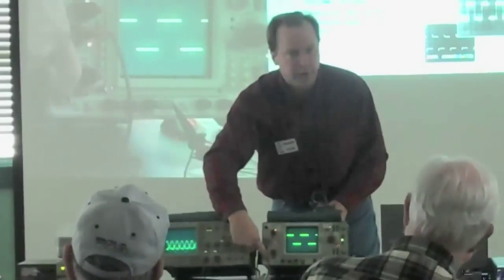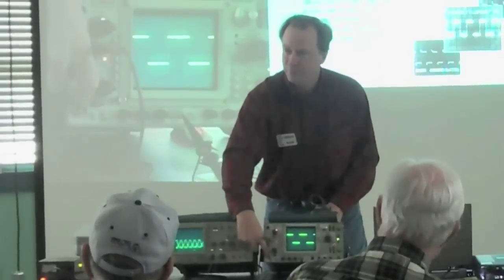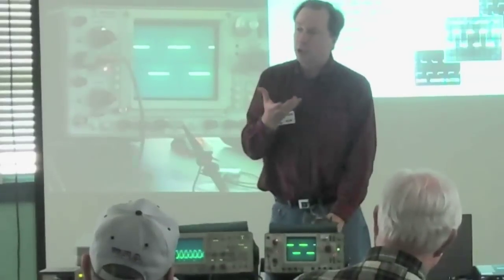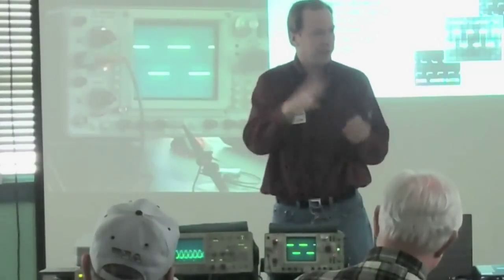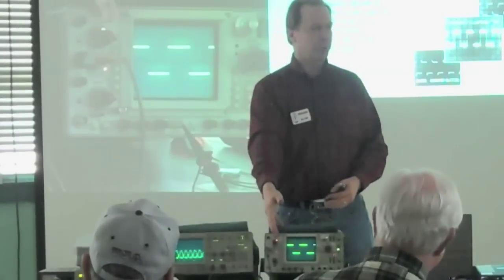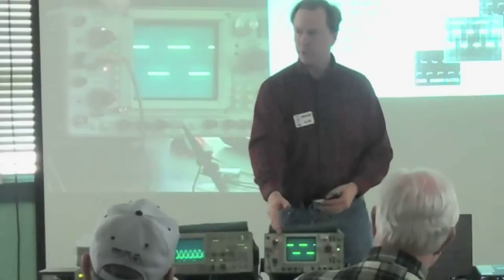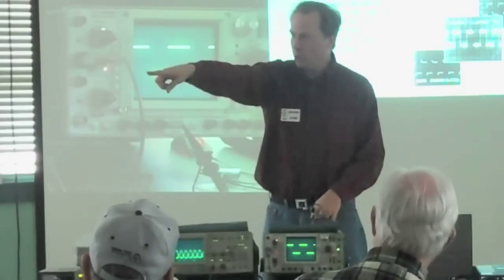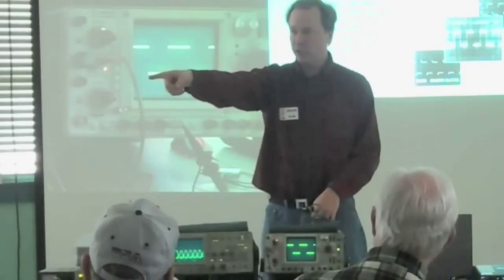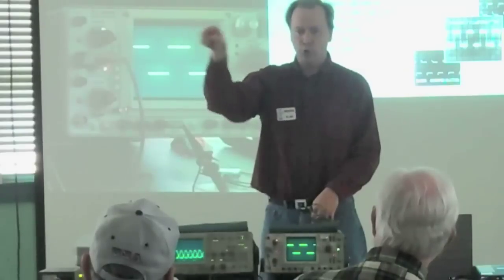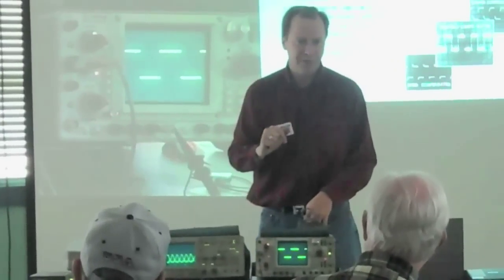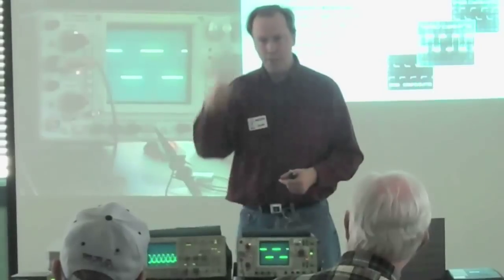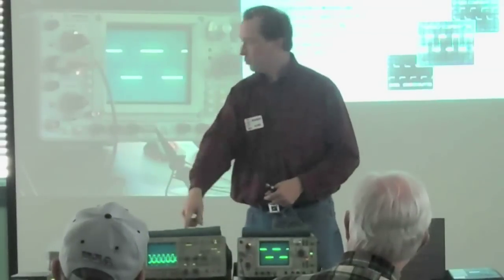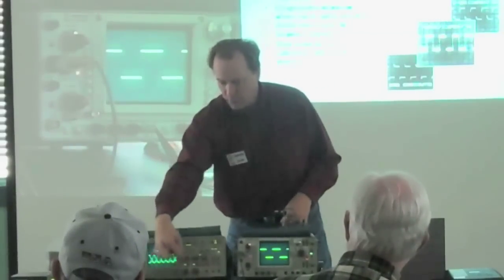Okay, a lot of the scopes will not have the little sensing ring around the BNC to do that for you. So you've got to take that into account when you're plugging your 10x probe in, that you've just increased your volts per division by a factor of 10. Even that little digital scope on the corner there, it's a Tektronix scope, but it doesn't have the sensing ring. You have to go to the vertical menu and tell it there's a 10x probe attached. For some of these other scopes, you just have to know mentally that you did that. This particular scope here, the readout is on the screen and it changes automatically when you attach the probe.